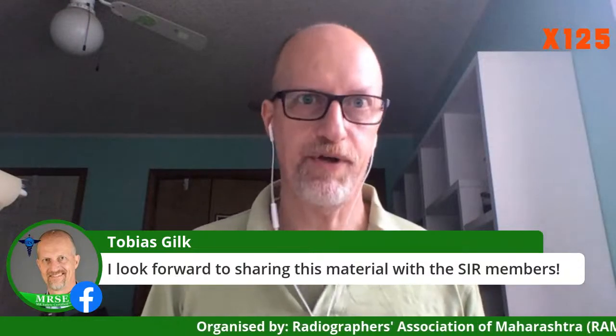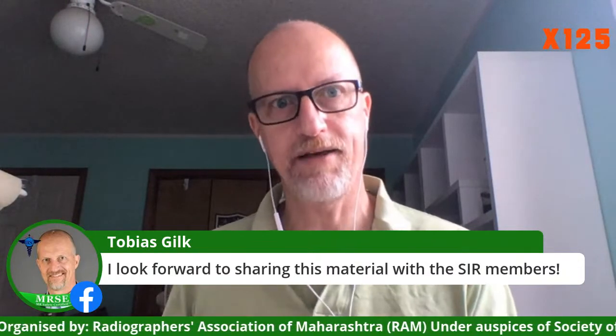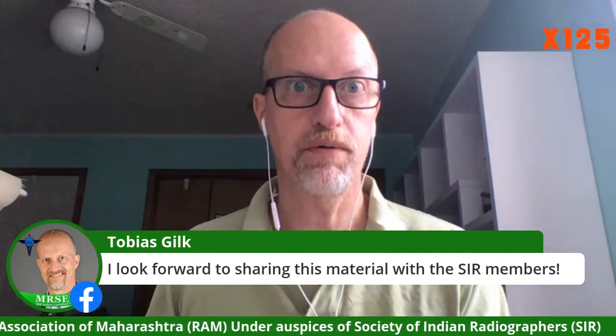We're going to break these 3 electromagnetic fields down and talk about them individually because they are independent of one another. Successfully addressing risks associated with static field does nothing for gradient magnetic fields, and that does nothing for radio frequency magnetic fields, with a couple of exceptions. But in general, we should approach each of these as being completely independent electromagnetic fields, as they are, with completely independent sets of risk assessment and risk mitigation.